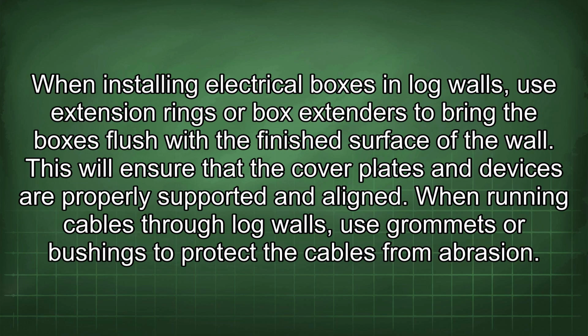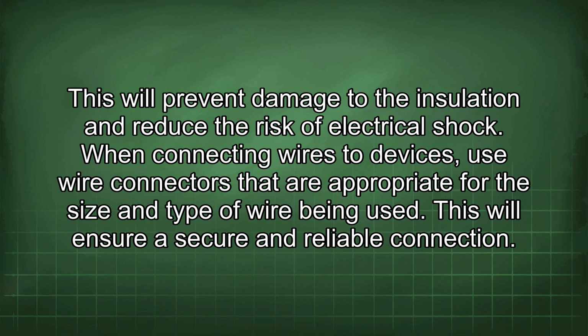When installing electrical boxes in log walls, use extension rings or box extenders to bring the boxes flush with the finished surface of the wall. This will ensure that the cover plates and devices are properly supported and aligned. When running cables through log walls, use grommets or bushings to protect the cables from abrasion. This will prevent damage to the insulation and reduce the risk of electrical shock.